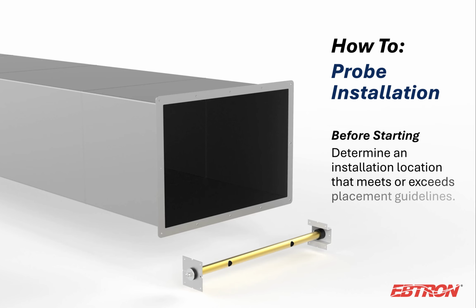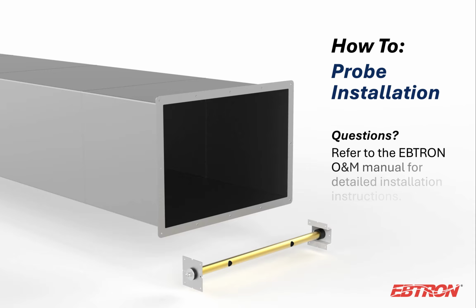Before getting started, be sure to determine an installation location that meets or exceeds EBTRON's recommended placement guidelines. Specific placement guidelines can be found in the O&M manual or by utilizing the EBTRON placement tool. If the location does not meet or exceed placement guidelines, the installed accuracy may be compromised and field adjustment may be necessary. Further detailed installation instructions can also be found in the O&M manual. Please consult directly with EBTRON or your local EBTRON representative when any questions arise during installation.